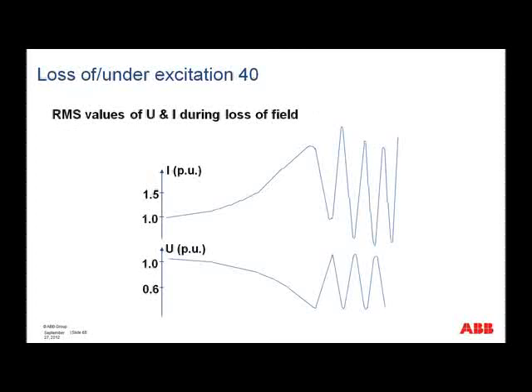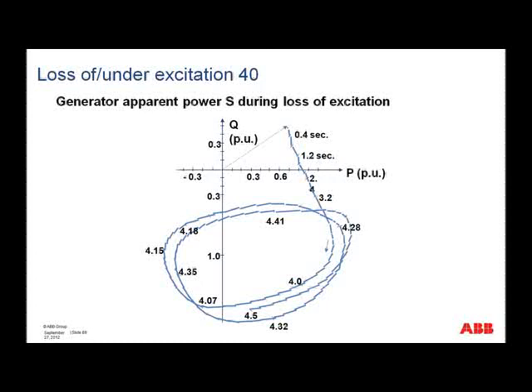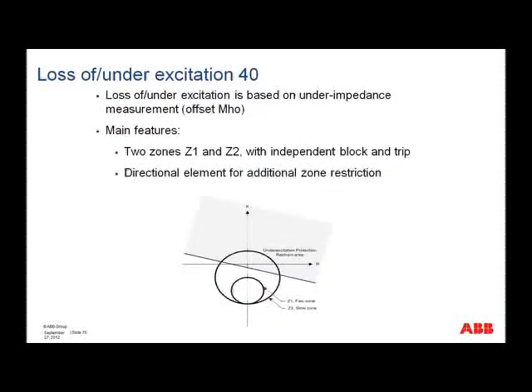This slide just shows what the measured RMS values of voltage and current would look like at loss of field. And if we view that in the S-plane, it looks a little bit like this. So what protection do we apply? Well, generally we have these two zones of underimpedance, offset MHO, and also this directional line. And the main purpose of this directional line is really to create or to achieve additional stability, because it will be a restrained area.